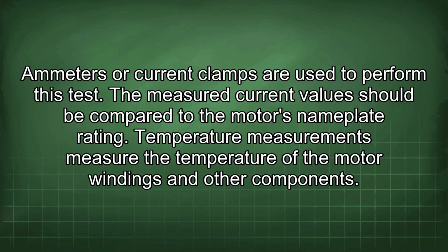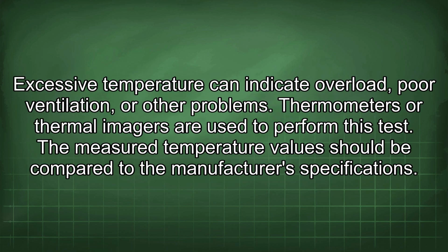Temperature measurements measure the temperature of the motor windings and other components. Excessive temperature can indicate overload, poor ventilation, or other problems. Thermometers or thermal imagers are used to perform this test. The measured temperature values should be compared to the manufacturer's specifications.